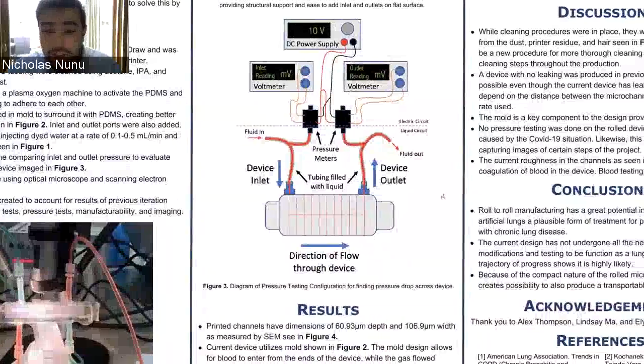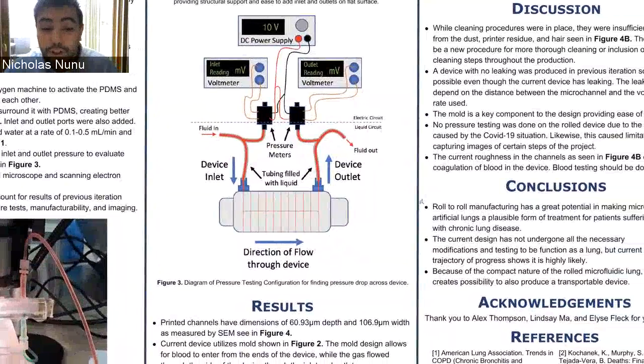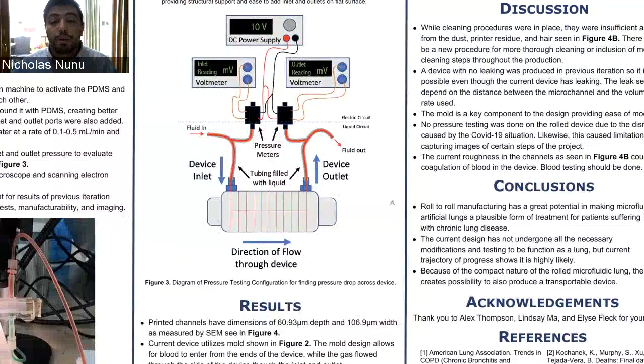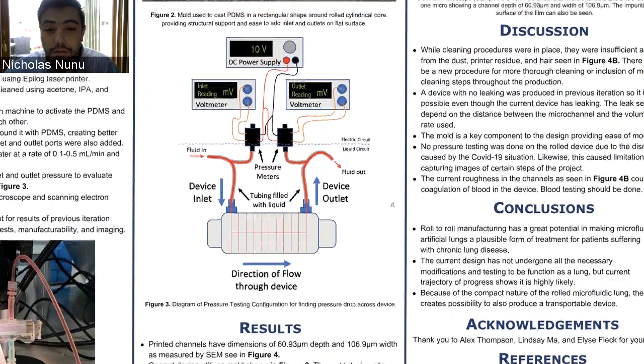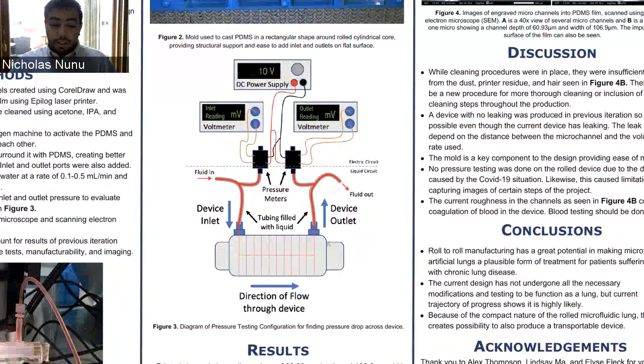Another test we can conduct is a pressure test, to see the pressure drop across the device. This is similar to the flow test setup, but these also have pressure meters that measure the pressure of the fluid going into the device and coming out of it. Using this, we take the difference between these two values, along with a calibration and conversion value, to turn the millivolt reading into a pressure reading.